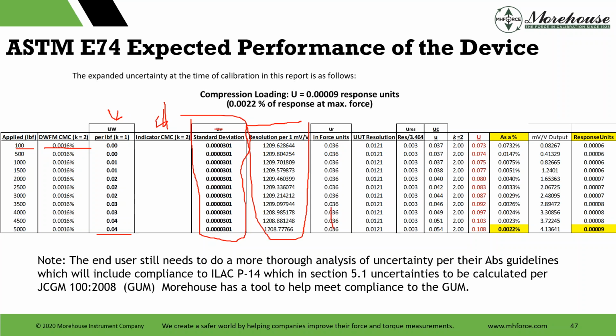There we have what we have, 036. UUT, it's constant because the lower limit factor is constant for the whole loading range. Then you have the resolution, and now you combine them. UC is combined. So we combine everything. We sum the squares of all of this stuff, and we multiply it by k equals 2, and by multiplying it we get U. We get our uncertainty here that varies, and you can see it varies.